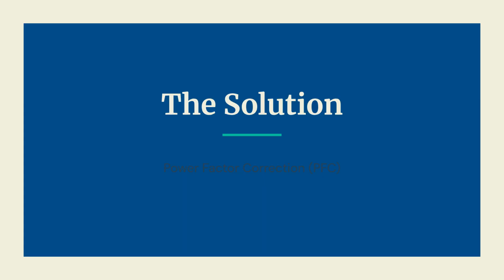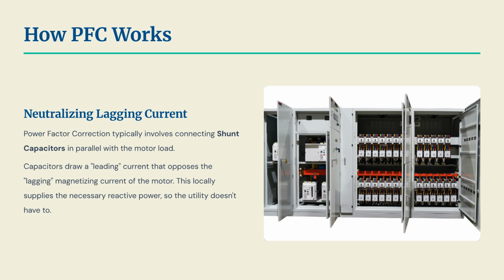The solution to low power factor is power factor correction, or PFC. PFC works by connecting shunt capacitors in parallel with the motor load. These capacitors draw a leading current that neutralizes the motor's lagging magnetizing current, supplying reactive power locally.